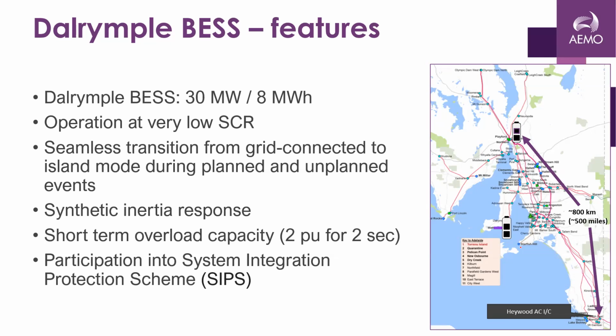It has a very low short circuit ratio, right? Because it's the tail end of the line. It has shown a seamless transition, that's the word people use nowadays, from grid connected to island mode, during a planned disconnection of the upstream network and an unplanned disconnection of the upstream network. It has proved synthetic inertial response. I'll show you that in the next slide. It has a short-term overload capacity, 2 per unit for 2 seconds.